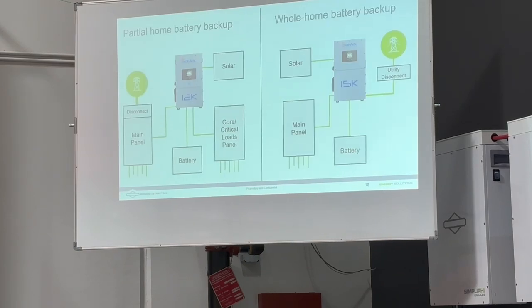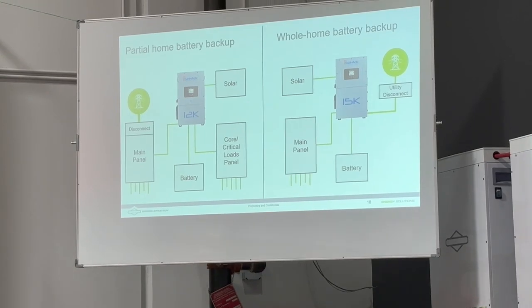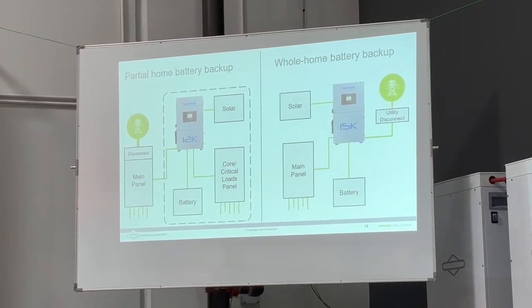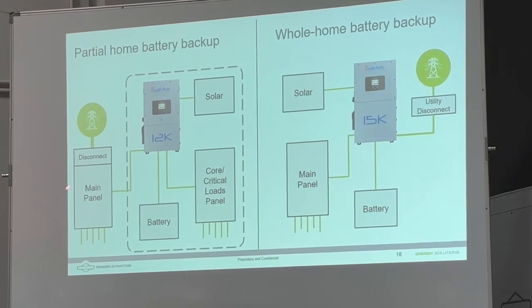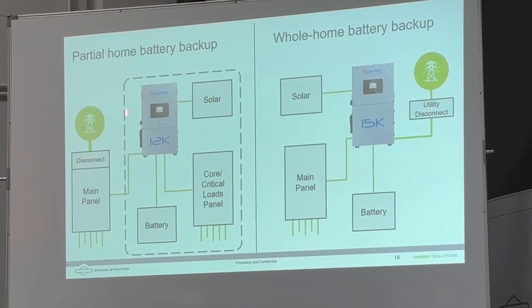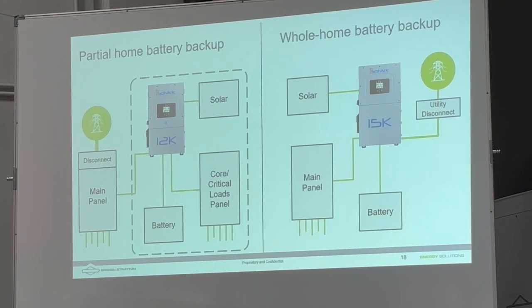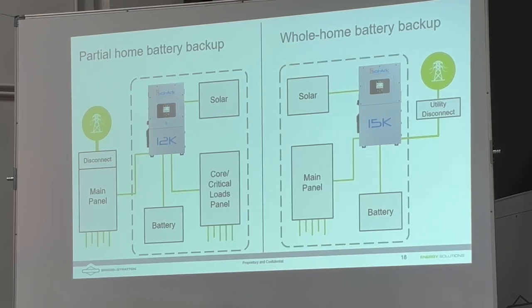When we get to inverters, load management looks very different. You will do it potentially based on how much energy is left in your batteries, and if your batteries are draining quickly, you might drop off loads based on that. That's where you use the Span, the Lumin, the Savant panels to do load management. So we talked about disconnecting from the grid. In a grid down event, this dashed line shows that in a partial home backup system with an 8K, a 12K, or a 5K Sol-Ark inverter, you would be isolating just the critical loads panel, and no power from the inverter would be going back out to the main panel or the grid. That means the whole main panel would be down in a grid down event, right? You're not backing up the whole home. The 15K really changed that game.